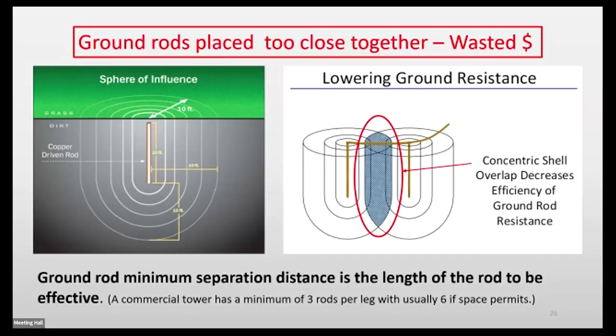Here we don't have to worry too much about frost line. In the Midwest where I came from, the grounds had to be dug deep enough that the top of the ground line was down at frost line, 6 to 7 feet down. So imagine how deep those rods went, because up in the frost area you'd effectively lose the ground rod's effectiveness.